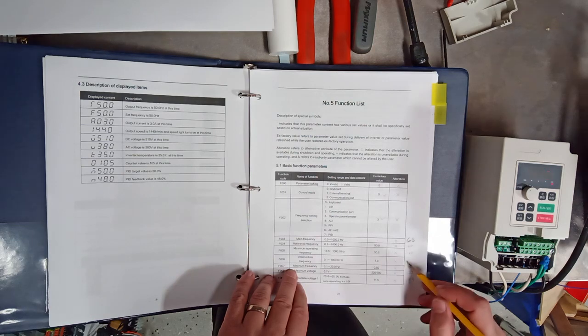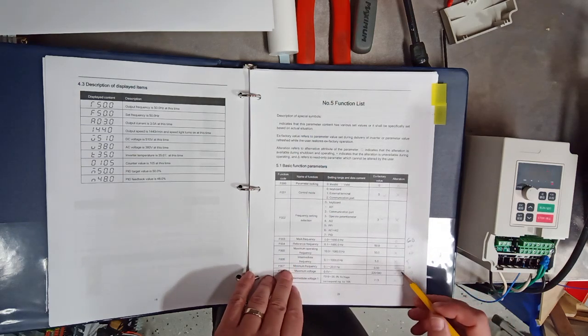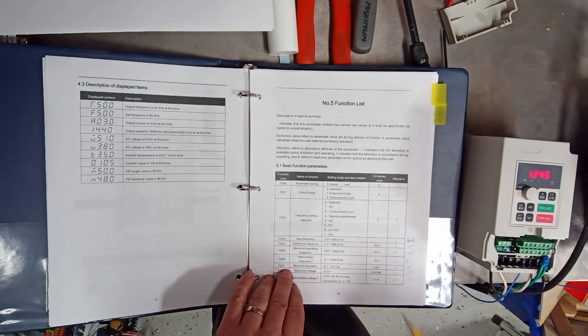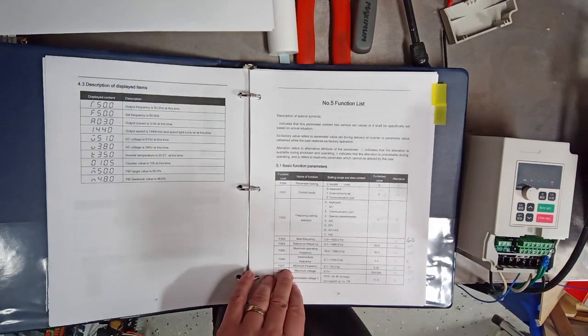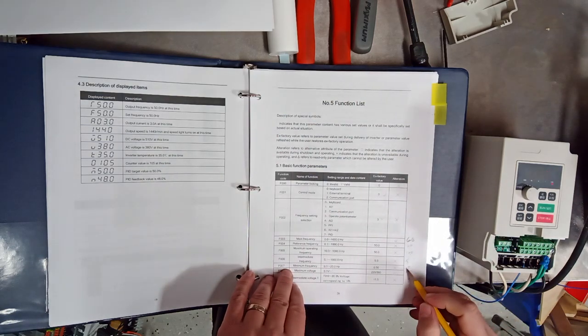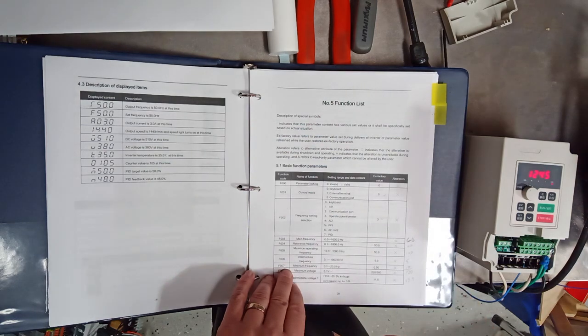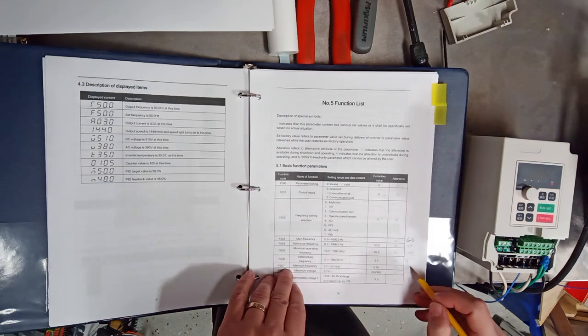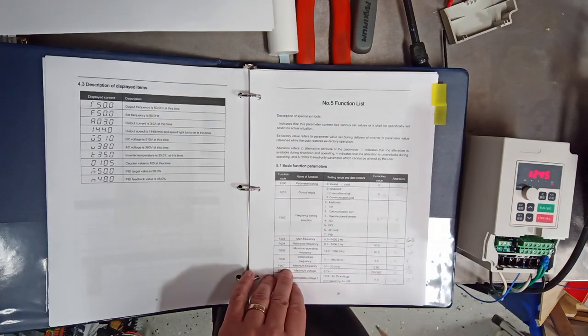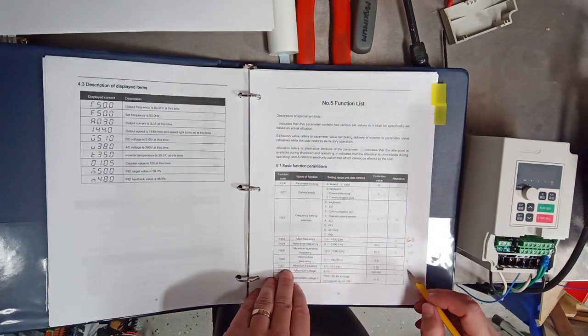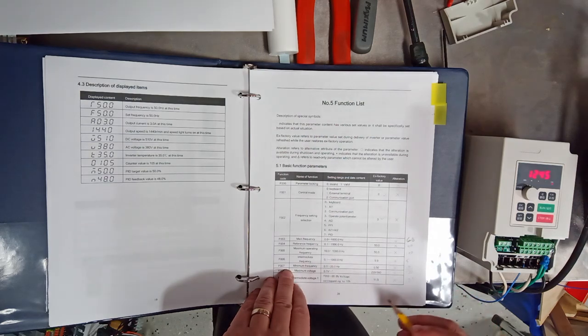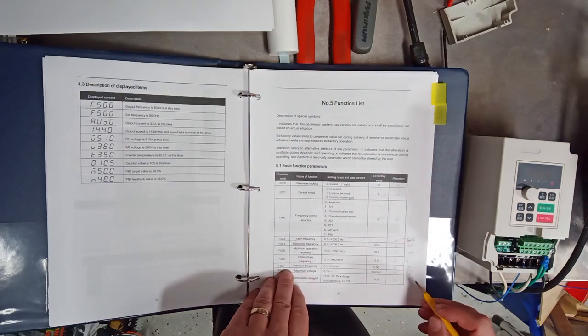The rest of these values, you can see that I've recorded some of these down. Like this one is 5, I left it at 5, it came in as 5. Minimum frequency. I'm setting my minimum frequency to 10 Hz in the video you saw as I slowed it down to 500 RPM. If I was getting into there and bogging it down, the current would start to increase. So that minimum frequency is what you want to set as your minimum RPM, where you know that if you're going to be bogging it down, you don't want to get too low. So I set mine up at 10, and that might be reasonable. If you've got a 3600 RPM, you might have to set that up and accept a little higher RPM as your minimum.